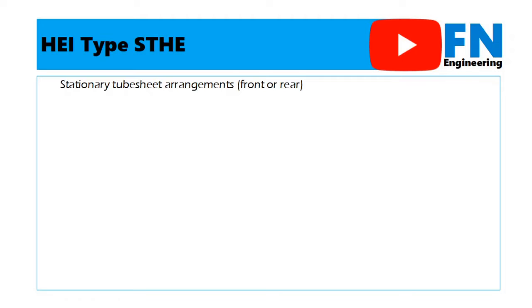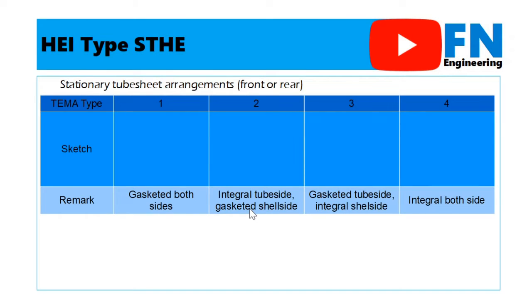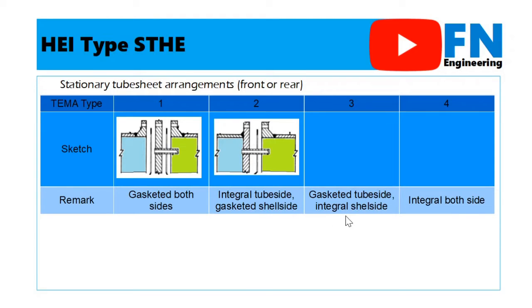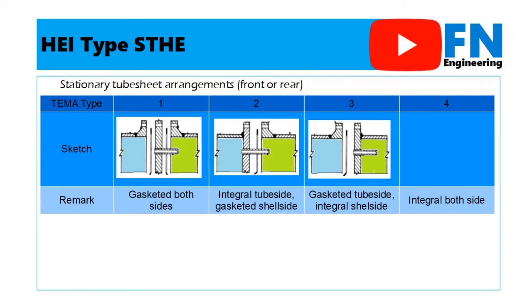The first is the stationary tube sheet arrangement. It can be in the front head or rear head. There are 4 types of stationary tube sheet arrangement. First is type 1. It is using a gasket on both sides, tube side and shell side. Type 2 is tube sheet integrated with tube side and using a gasket in the shell side. Type 3 is the opposite of type 2. Lastly is type 4. In this type, the tube sheet is integrated with both sides, tube side and shell side.